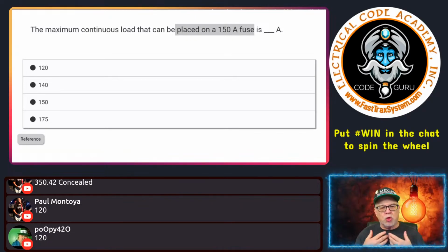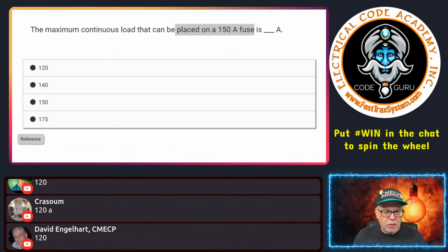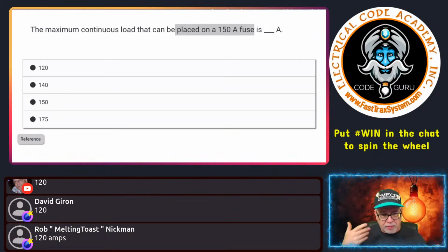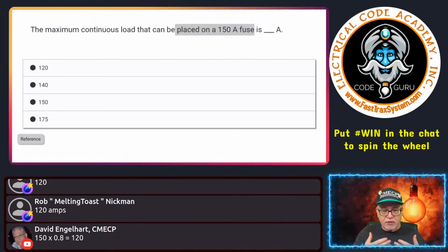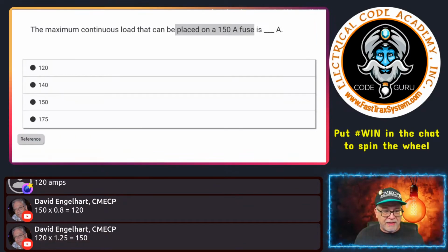Right? Because we know the rules, whether it's in 210 or 215, in general, when we're talking about a continuous load and overcurrent protected devices, it's also covered. And this one we'll assume is just a typical branch circuit because it didn't state otherwise, not that it's going to matter because it's the same principle. We know that we can't load an overcurrent protected device more than 80% of it. Or, if you knew the conductor, you do it at 125%, right? But since we know the overcurrent protection, we're going to limit it to 80%, which is the reciprocal of 125.